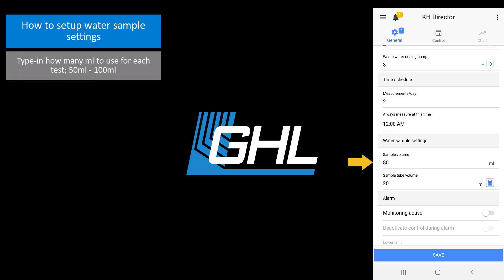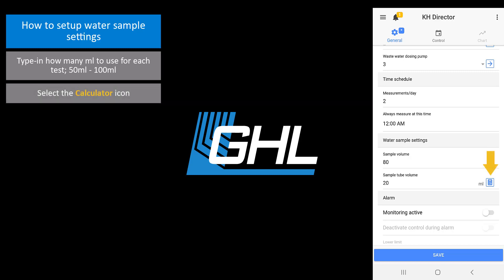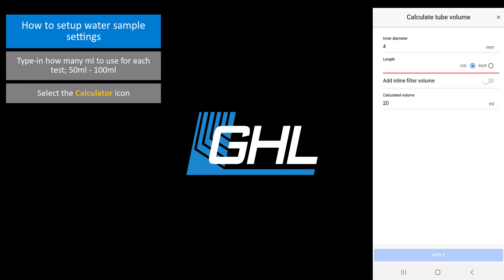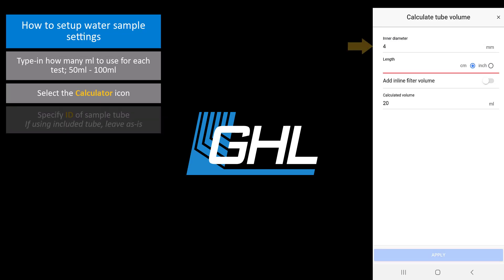Now let's set up the water sample settings. In the Sample Volume field, type in how many milliliters you want the KHD to use for each test. This can be anywhere between 50 milliliters and 100 milliliters. In the Sample Tube Volume field, press the calculator icon. Here is where you tell the KHD how many milliliters the water sample tube holds. If you are using the sample tube that was included with your KHD, you can leave this field as is.